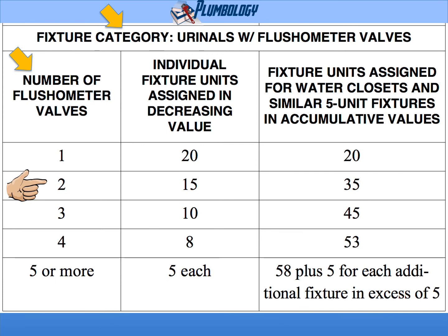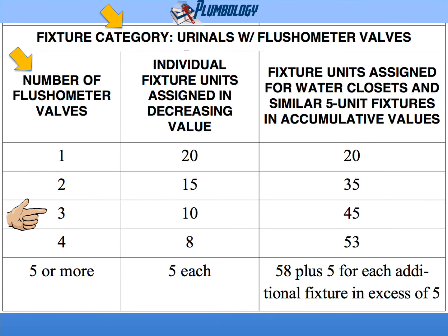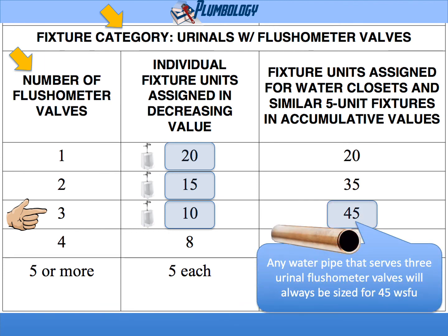If we have two urinal flushometer valves, the first one still takes the place of 20 fixture units. The second one will be 15 water supply fixture units, and the accumulative value will be 35. So any water pipe that serves two urinal flushometer valves will always be sized for 35 water supply fixture units. If we have three urinal flushometer valves, the first is 20, the second is 15, the third will be worth 10, and the accumulative value will be 45. So any water pipe serving three urinal flushometer valves will always be sized for 45 water supply fixture units.